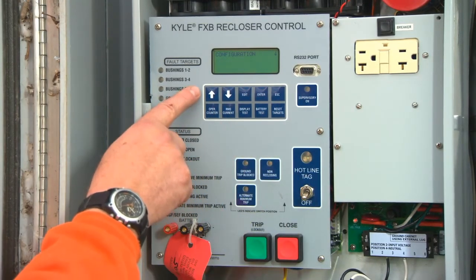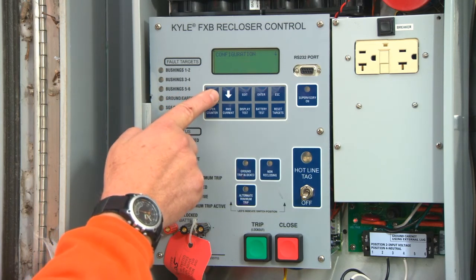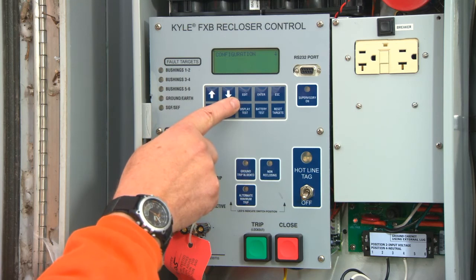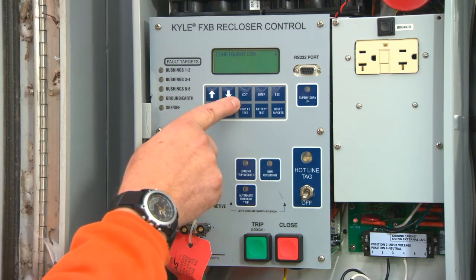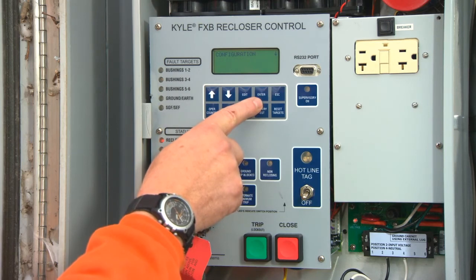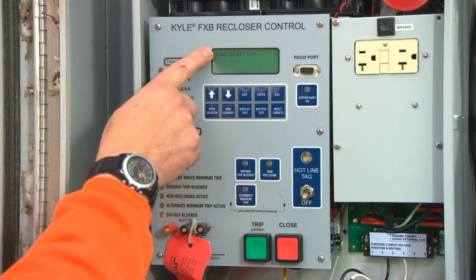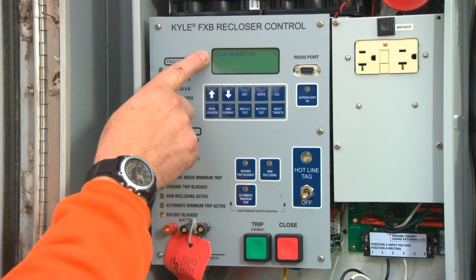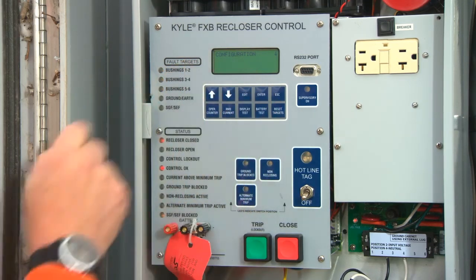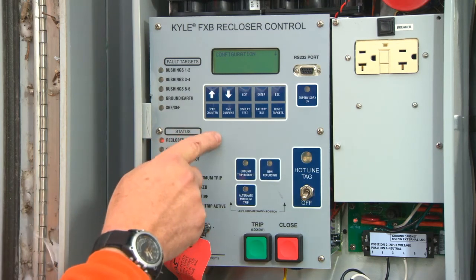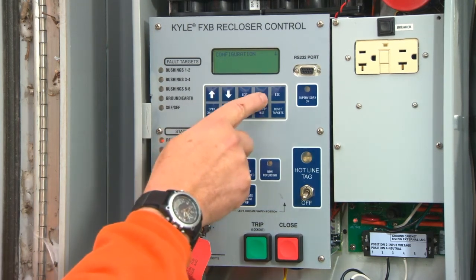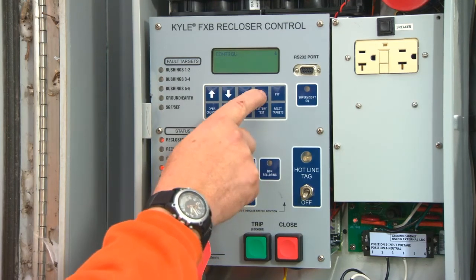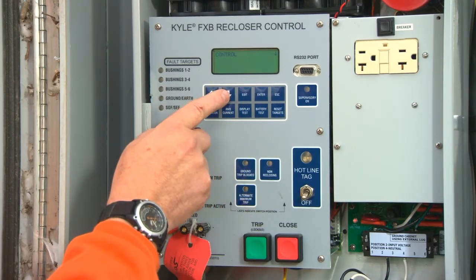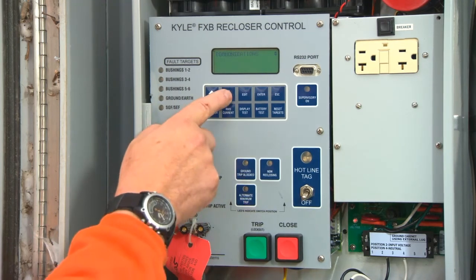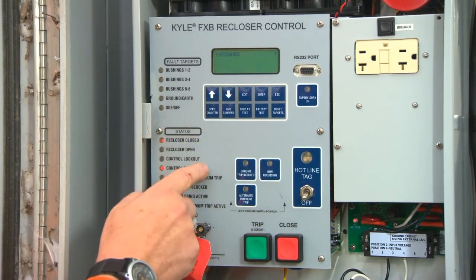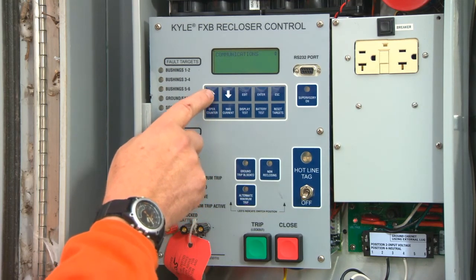Across the top of the control are more selection items. From left to right are the up and down selection buttons and the Edit button, used to change control settings. Next is the Enter button, which allows you to access whatever features are currently available on the display, followed by the Escape button, which allows you to return to the main menu. After pressing the Enter button, you can scroll through selections using the arrow keys, such as Control, Recloser, Communications, and Password. Let's scroll back up to Control and press Enter.